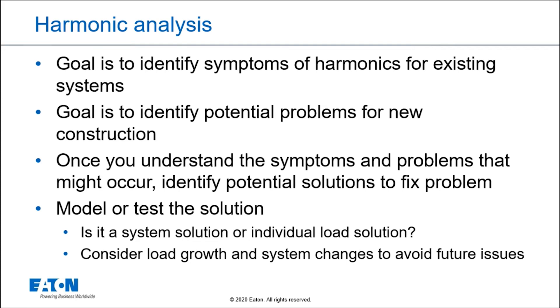If you're doing the harmonic analysis, the goal for an existing system is to identify the symptoms of harmonics. If you're looking at new construction, you're going to look for possible problems related to harmonics. Once you understand the symptoms of the problems that might occur, identify the potential solutions that can fix the problem. Then you model or test the solution depending on if it's new construction or an existing system — and consider whether it's a system solution on the main bus or in front of an individual drive. Make sure you consider that loads will change — account for load growth and avoid future issues, whether it's more load or less load.